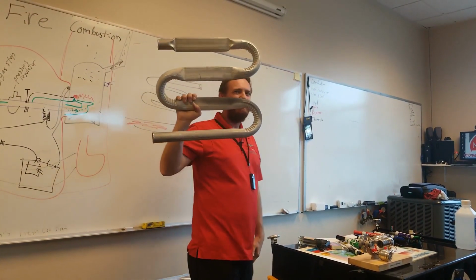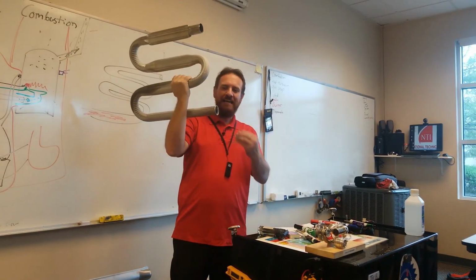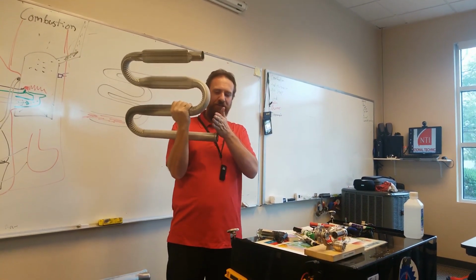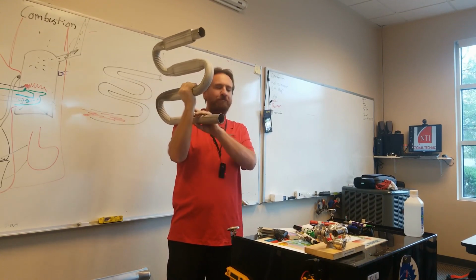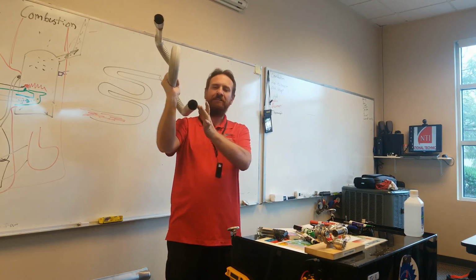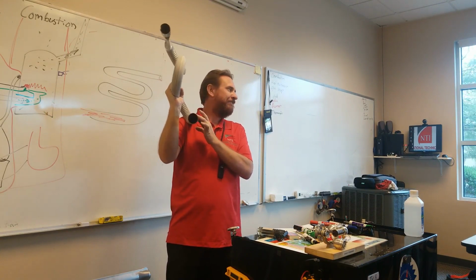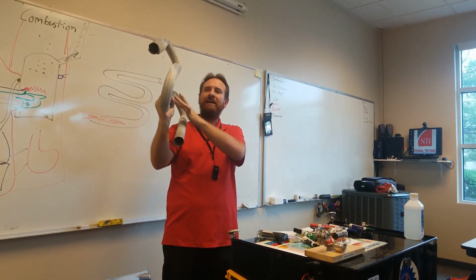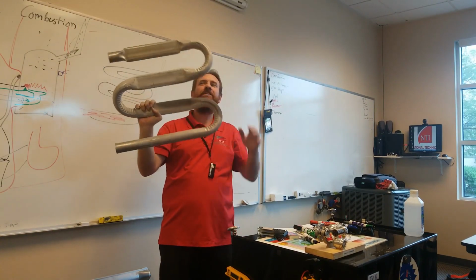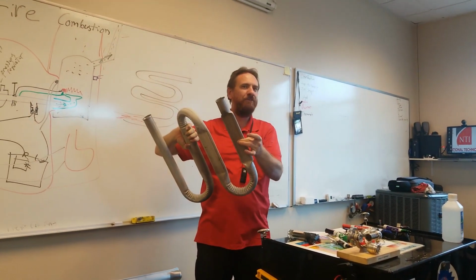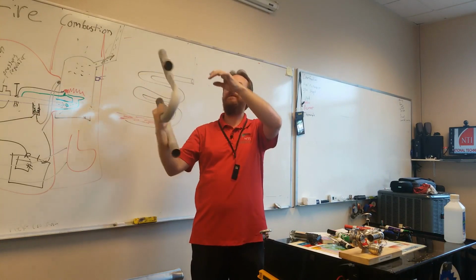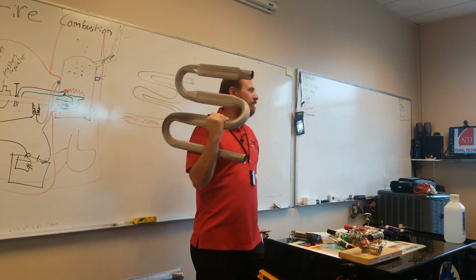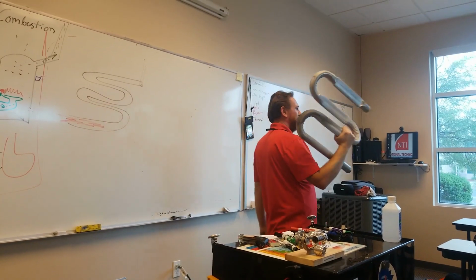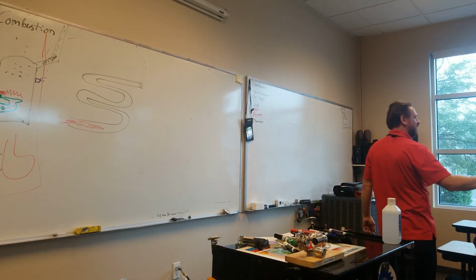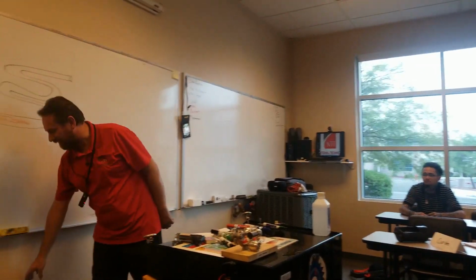This is the heat exchanger. This is just one tube. I can actually blow the fire inside the tube. There's a chamber here. The fire's burning inside, and the air is blowing on the outside. The fire's only burning in this first chamber, but the gases from that fire are still hot. So the gases pull back and forth and back and forth. And then notice how we squeeze the pipes towards the end. Well, by squeezing the pipe, I have more gas touching more metal. I get better heat transfer. This is one style of heat exchanger. The fire burns on the inside of that pipe, and on the outside of that pipe is the air.